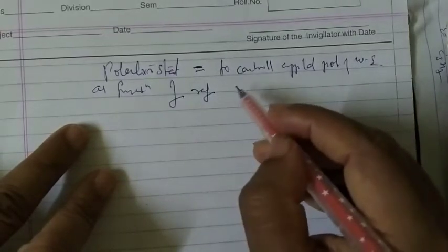Choosing and polishing the electrode is very important. The potentiostat is used to control the applied potential of the working electrode as a function of the reference electrode potential. The working electrode is composed of a redox-inert material, and its potential range is selected based on the experiment.